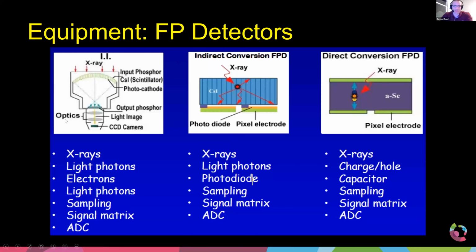So what are the pros and cons here? So the image intensifier, or the II, well, actually this is how, forgive me, that's the next slide. I got a little ahead of myself. So how do the systems create the image? Well, I just kind of talked about the photons come in, cesium iodide converts the light to electrons, so they are accelerated through, and then the image comes out on the back end.